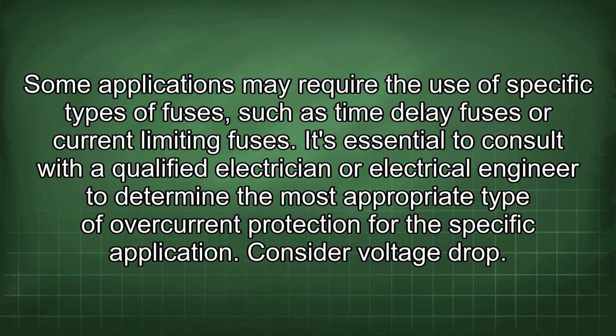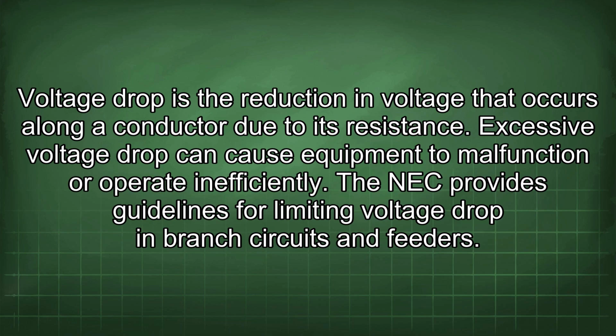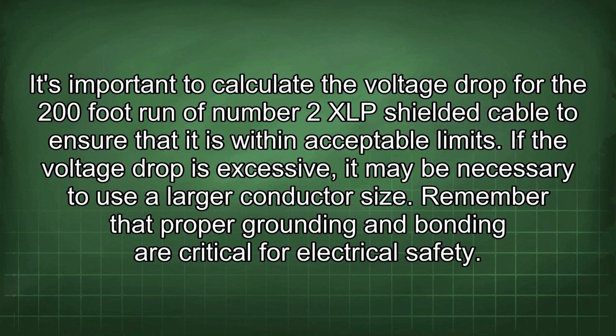Consider voltage drop. Voltage drop is the reduction in voltage that occurs along a conductor due to its resistance. Excessive voltage drop can cause equipment to malfunction or operate inefficiently. The NEC provides guidelines for limiting voltage drop in branch circuits and feeders. It's important to calculate the voltage drop for the 200-foot run of number 2 XLP shielded cable to ensure that it is within acceptable limits. If the voltage drop is excessive, it may be necessary to use a larger conductor size.